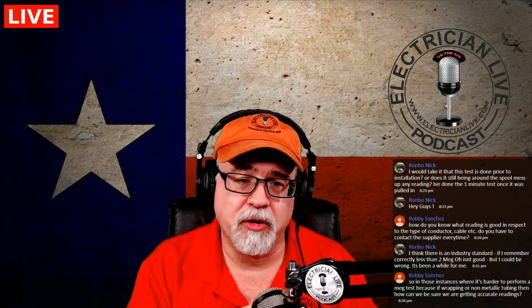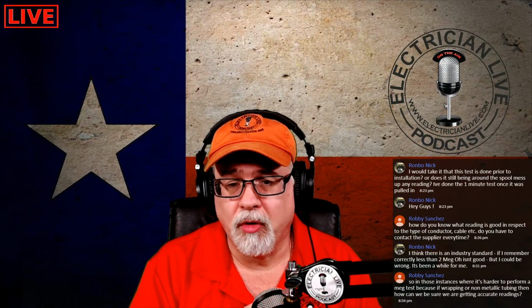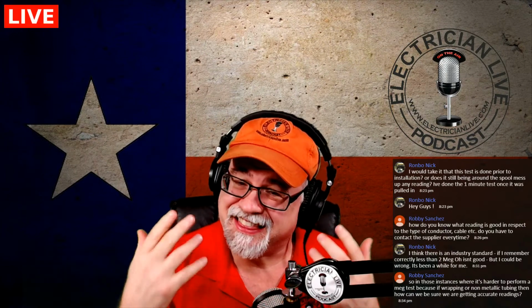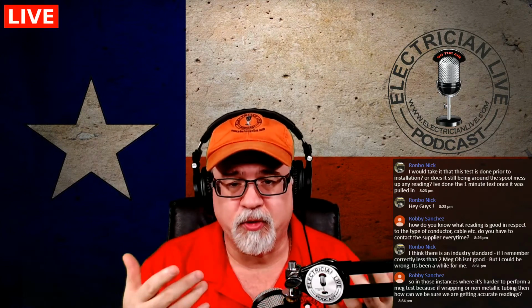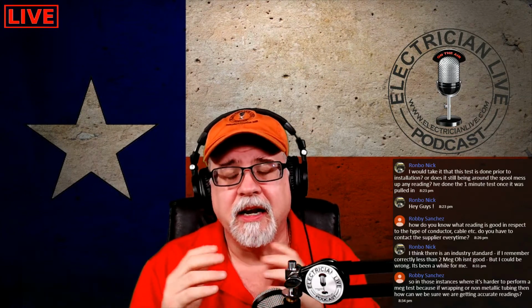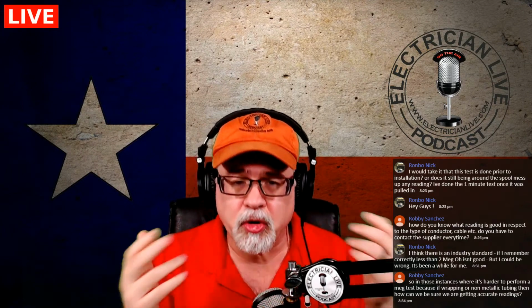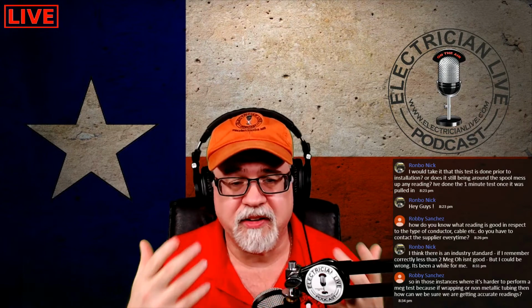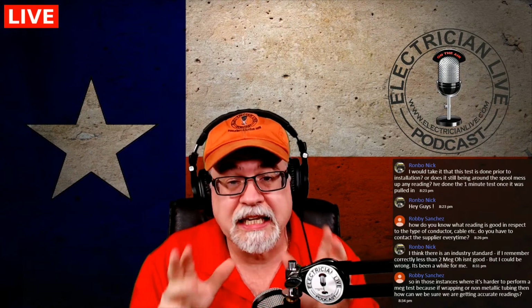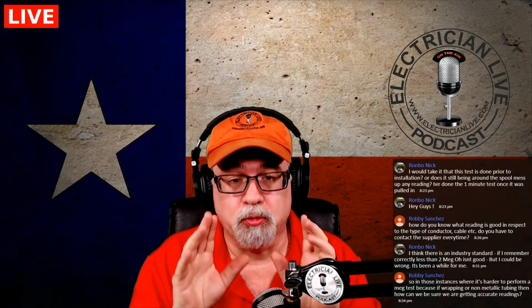Now, the people that I talk to, the megohm testers, megohm meters, the meg meters, they have told me that their products weren't originally designed towards low voltage wiring. It was really designed for transformers with a separator or motors with the winding separations, appliances that could cause a failure between the insulation to the metal housings. Those type of tests was really what they were designed for. Now, they work really well. Meg meters work really well on medium voltage. They work really well on high voltage.